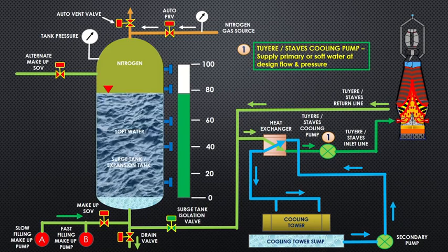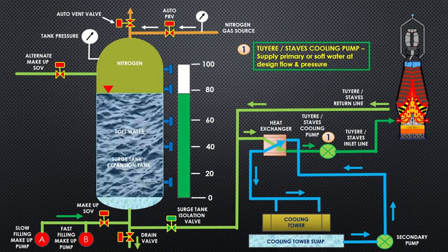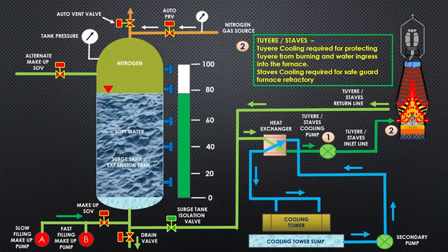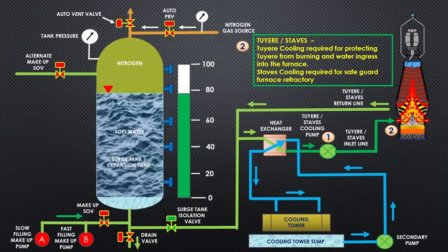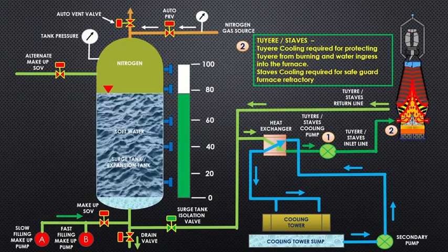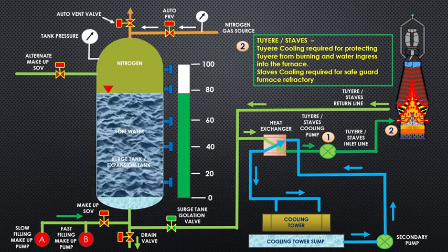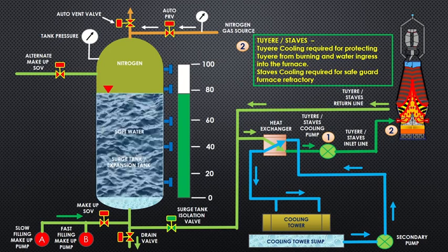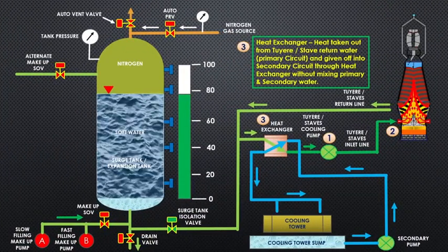Surge tank has the following components. We will discuss one by one. Tuyere or staves cooling pump supplies primary or soft water at design flow and pressure. Tuyere or staves cooling is required for protecting tuyere from burning and water ingress into the furnace. Staves cooling is required to safeguard furnace refractory.